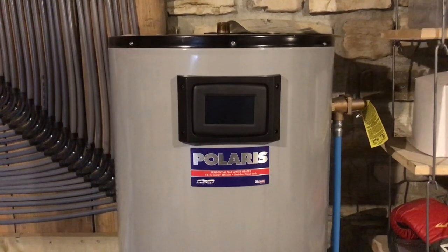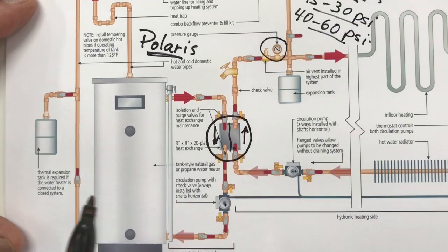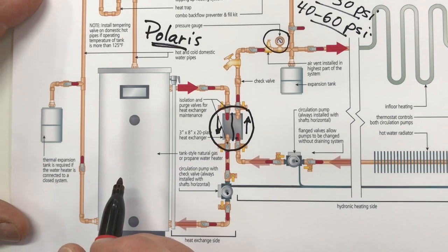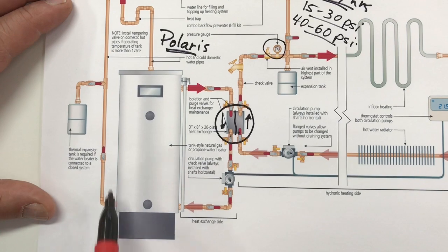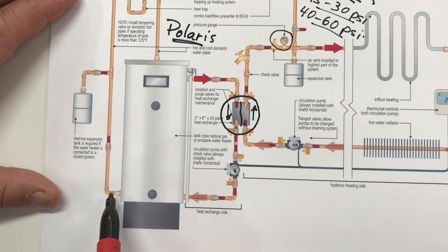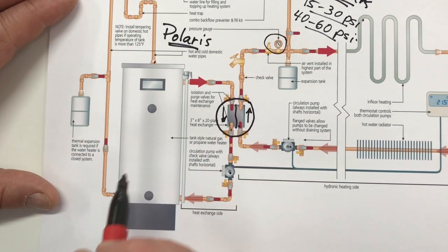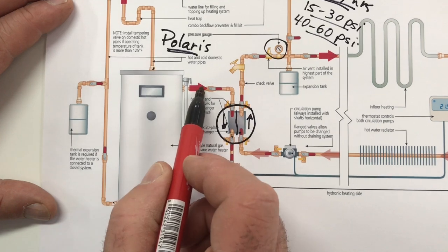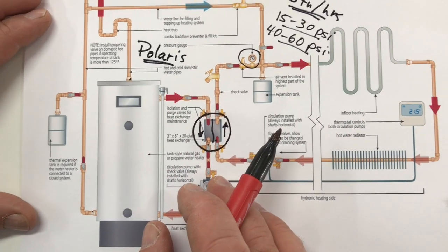The unit that I'm using is called the Polaris and it's made by a North American company called AO Smith and they specifically build this tank style water heater for this application. That's one reason they put on two pairs of taps here. We have the cold and the hot for your domestic side and then the return and the outflow here on the side of the tank for your hydronic heating system.